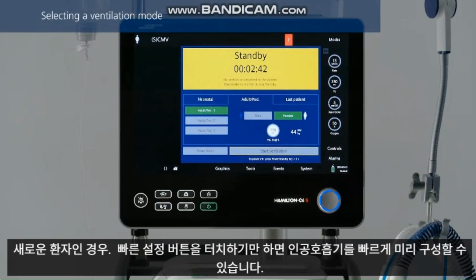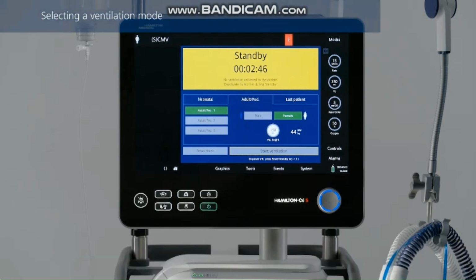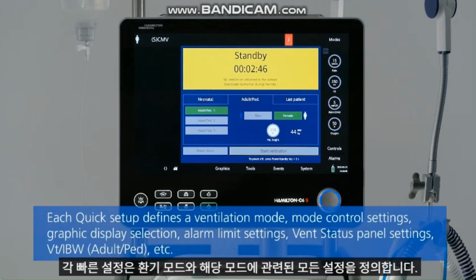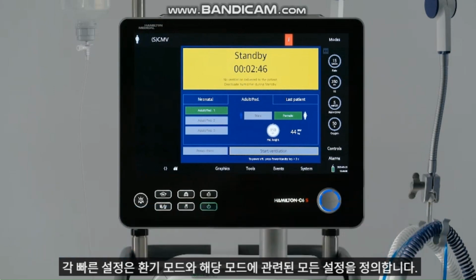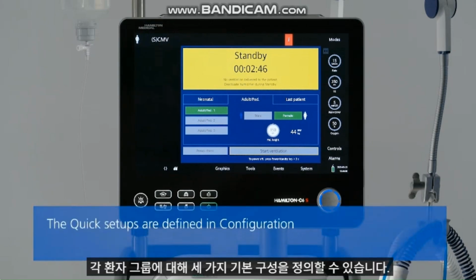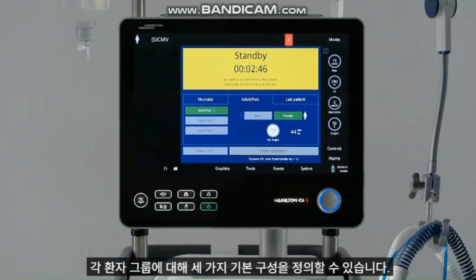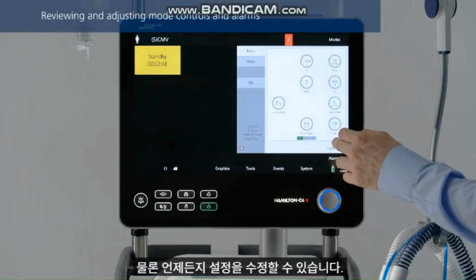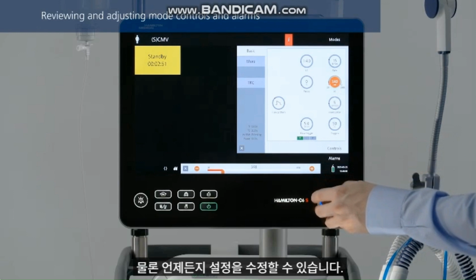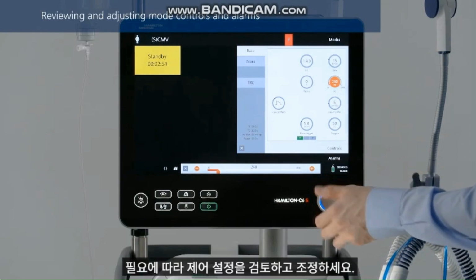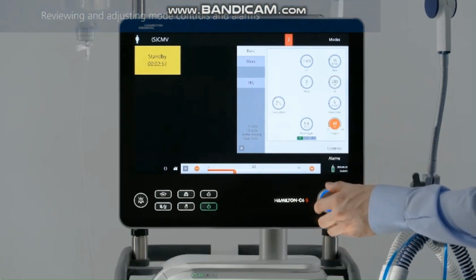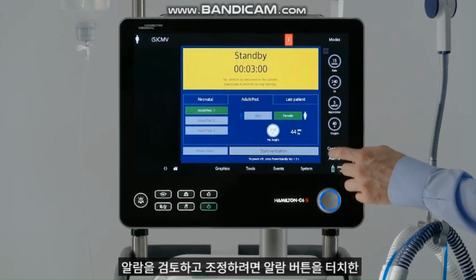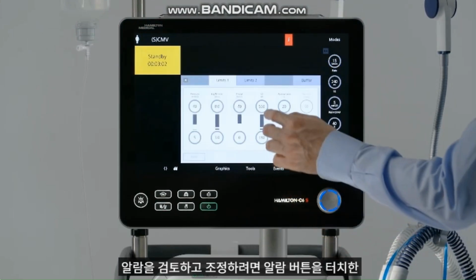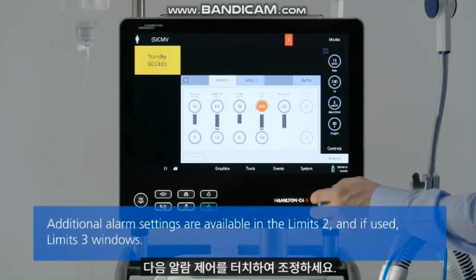For a new patient, you can pre-configure the ventilator quickly just by touching a Quick Setup button. Each quick setup defines a ventilation mode and all the settings relevant for that mode. For each of the patient groups, 3 different default configurations can be defined. Of course, you can always modify any of the settings. Review and adjust the control settings as needed. To review and adjust the alarms, touch the Alarms button. Then, touch the alarm control and adjust it.